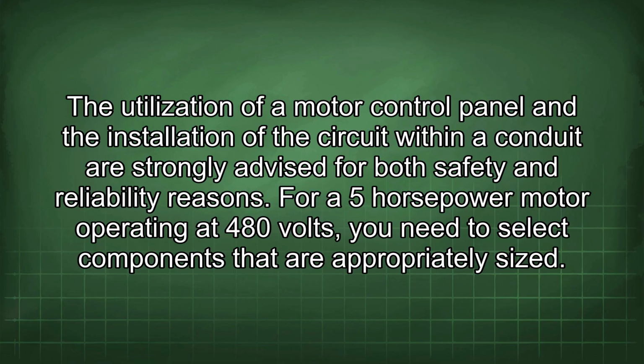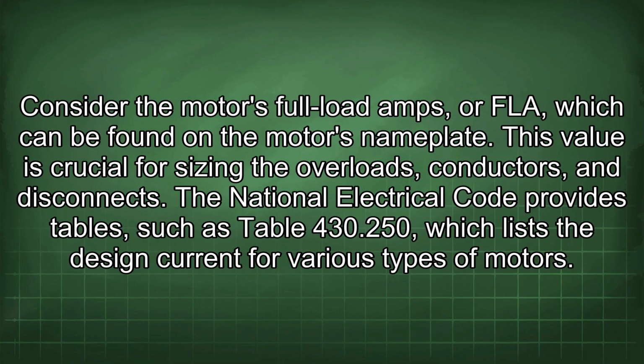For a 5 horsepower motor operating at 480 volts, you need to select components that are appropriately sized. Consider the motor's full load amps, or FLA, which can be found on the motor's nameplate. This value is crucial for sizing the overloads, conductors, and disconnects.